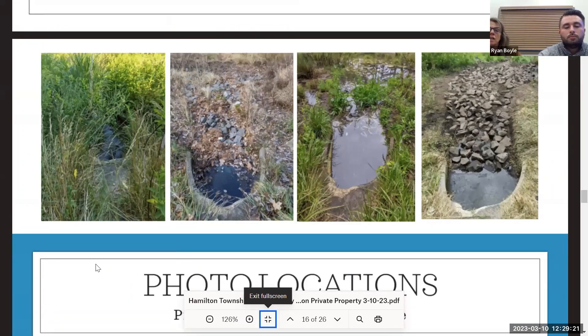One of the reasons we stress a photo location when doing inspections: when you take a picture from the exact same spot, it gives you the ability to track conditions over time. The same spot can look quite different before maintenance, after maintenance, and after a storm. One of the biggest strengths is knowing whether you need to perform maintenance or can continue to monitor. It may also highlight a new condition you didn't notice before — you can go back and look at previous photos to compare. It's very valuable and will help you plan and budget for maintenance.